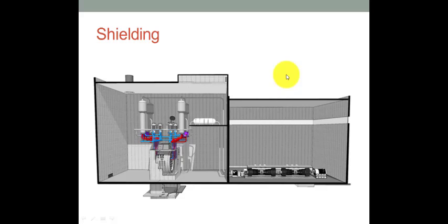Shielding is the next important component of the CANDU reactor. Uranium isotopes are not very radioactive by themselves and do not constitute a direct radiation hazard. You can safely hold a fresh CANDU fuel bundle in your hand. It is the fissioning process that creates the nasty radioactive fission products. These are dangerous and must be kept in isolation from us. We protect ourselves from them by thick walls that slow down and absorb neutrons. A combination of hydrogenous materials like water and hydrocarbons and absorbing materials are used as the shielding material.